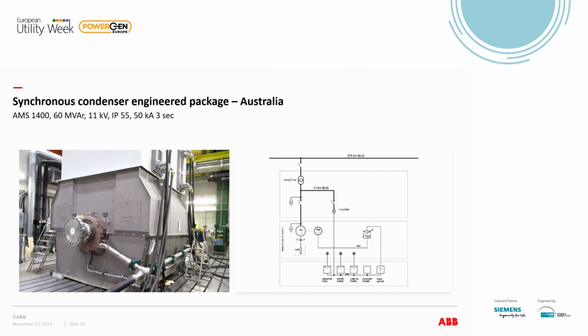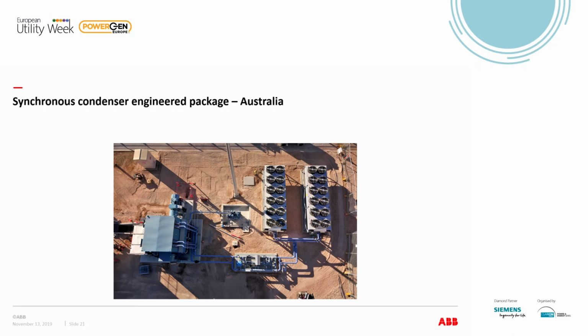Now, this is another installation. This is in our workshop where we do the FAT test, this final acceptance test of the machine. This condenser will be then connected via transformer to the transmission grid. And this is how it looks when it's at site. You have the big blue box, which is the condenser, and then we have this auxiliary equipment beside, which we also deliver. It's the cooling system, the lube oil system, the pony motor, and the control and protection panels with that.